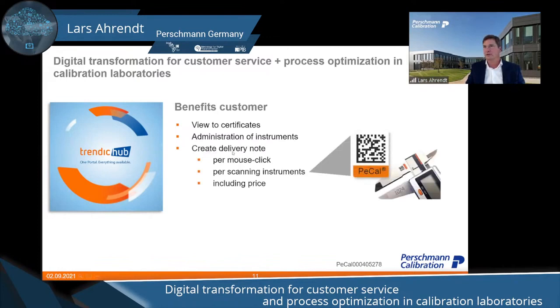He can create a delivery note to send the instruments to our laboratory, maybe also to another laboratory, but it's the best, of course, in the process if he sends the instruments to our laboratory. He can create the delivery note per mouse click. So he can select the several instruments in this administration software, but he can also scan the instruments. So we developed a small sticker, and this sticker is on all the instruments we calibrate. We put this very special sticker on the instruments, and you can scan that if you have a mobile with you at the moment.